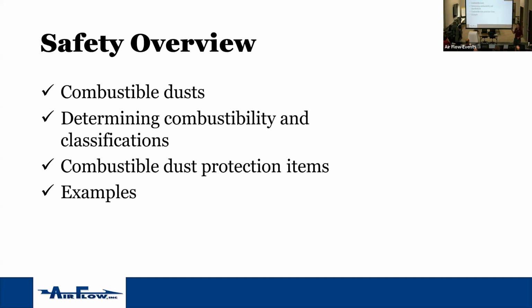As we progress through this, there's two things to remember. In dust collection, when you're talking about stopping a deflagration or an explosion, that's a completely separate set of devices, as is fire suppression or fire prevention. In dust collection, you can have a fire without having an explosion. You can also have an explosion without having a fire, or you can have both. So there's two completely separate entities to look at, and we'll walk through each one of them here and try and explain it a little bit.